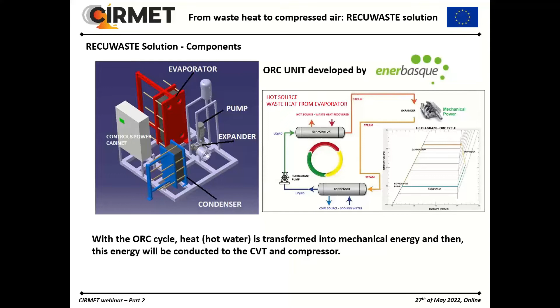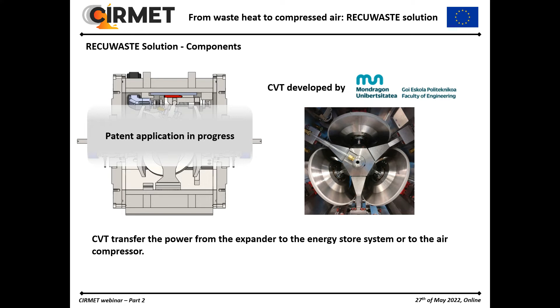A transmission mechanism is placed between the ORC and the air compressor, as you can see in this slide. The objective of the transmission system is to take the mechanical power of the expander and transfer it to the shaft of the air compressor. By means of a clutch and CVT, the torque and power can be modified and adapted depending on the needs of the RECUWASTE system. More details of this device will be presented by Ibai Eulacia from Mondragon University in the third webinar of this blog.